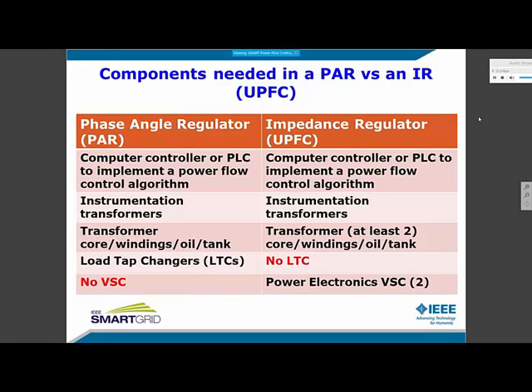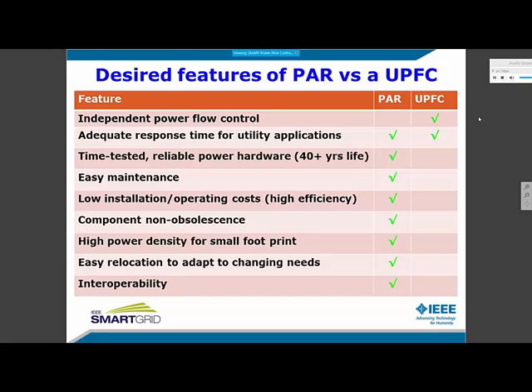Looking at the components in both the phase angle regulator and the unified power flow controller, which is an impedance regulator, we see that both require a computer for the control algorithm implementation, instrumentation transformers to sense voltage and current, transformer core, windings, oil, and tank. The PAR also requires LTCs, but no inverters, and the UPFC requires 2 inverters, but no LTCs. The UPFC offers the desired PQ flow control that makes the grid operate efficiently, and a PAR cannot offer that. It also offers the super fast response time from the inverters. Now, this is not needed in most utility applications, as we just saw. The PAR provides adequate response time using its LTCs.